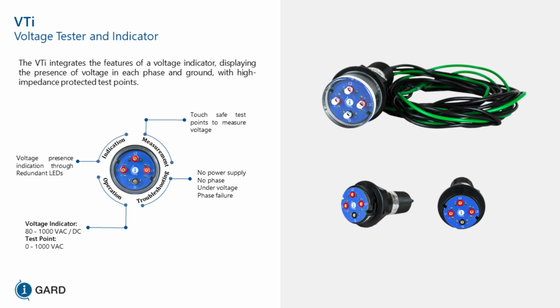The voltage presence is indicated through redundant LEDs. So you have visual indication that the voltage is live. There are 2 LEDs per phase, and they flash alternately, one on the positive AC cycle, one on the negative cycle. You have L1, L2, L3. So you have one conductor going to every single phase and one conductor going to ground. These are touch safe points, so you can measure the voltage. You can't put your fingers in there. You can only put the probes of the voltmeter in there. So we try to minimize shock when you do that.